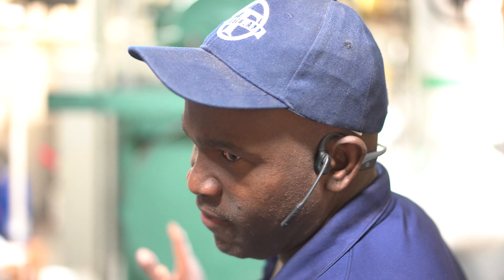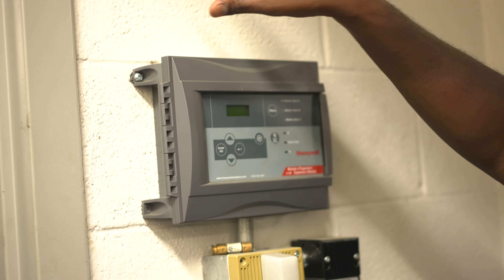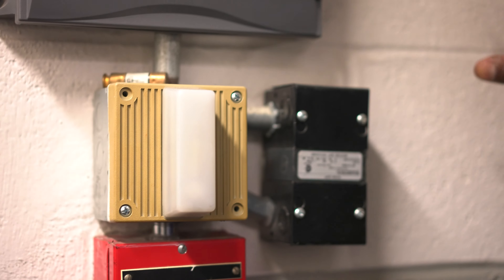If I'm running this piece of equipment, what people don't understand is, if there's a fire in this room, this is the bulb that goes. Check right outside this door — this is the alarm for a refrigerant leak in that system. This alarm should detect the refrigerant and open up vents to dump it outside this room. If the alarm does not go off, I'm supposed to break that glass right there, because that refrigerant is heavier than air and can suffocate everybody.